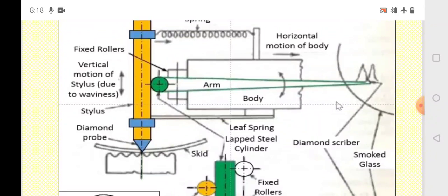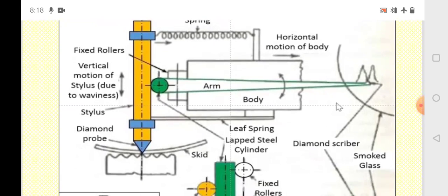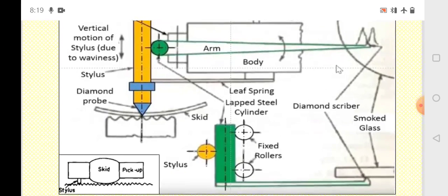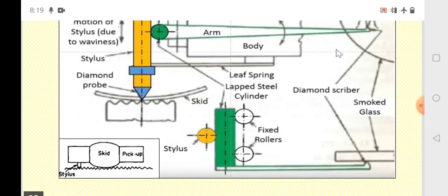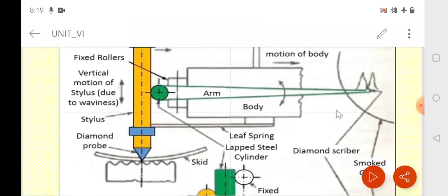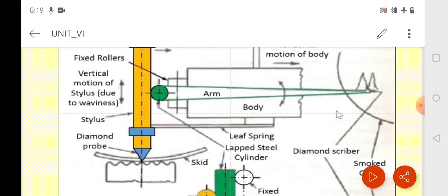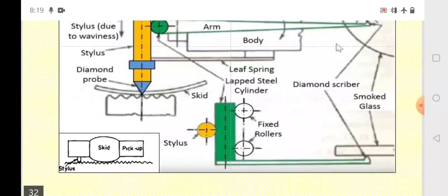So there is a probe here. This stylus is attached to a diamond probe. The tip is made of diamond and it is mechanically connected through this spring to this horizontal motion of the body and to this arm, which is fixed to this body, and with the help of this roller it is connected to this stylus also. As this diamond probe moves along the surface of the workpiece which is to be tested, we can plot this graph, or get the reading of this surface. We can get the profile of this surface and the roughness value.